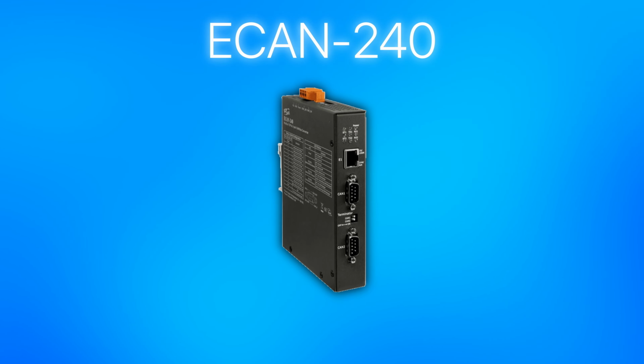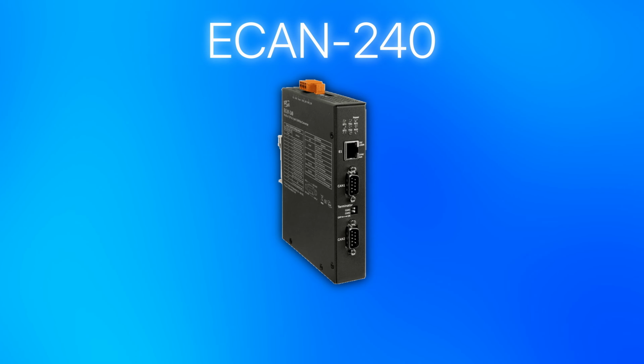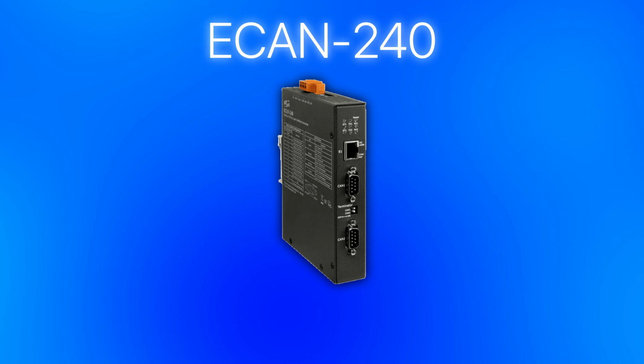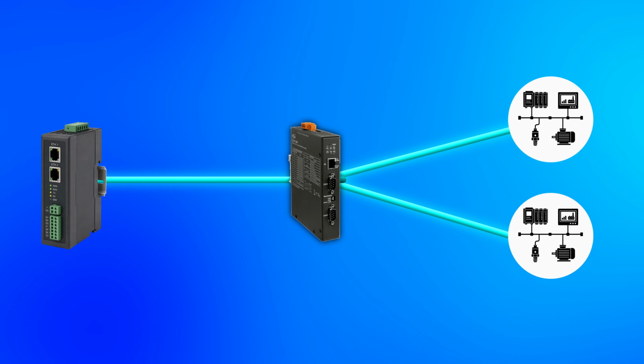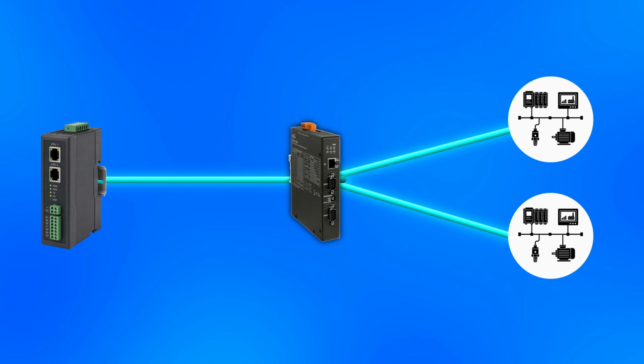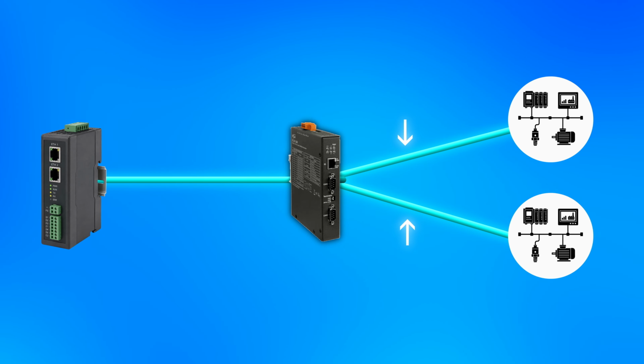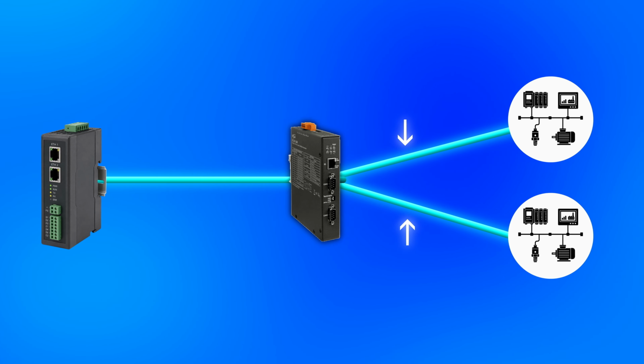Now, that handles the Modbus-to-CAN problem over serial. But what about getting CAN data onto your Ethernet network where your modern systems can actually use it? That's where the ECAN 240 comes in, and it's the most versatile module in the lineup for a reason. It's a Modbus TCP to 2-port CAN bus gateway, which means it gives you 2 independent CAN ports and puts them both on your Ethernet network through the Modbus TCP protocol that most industrial systems already speak natively.